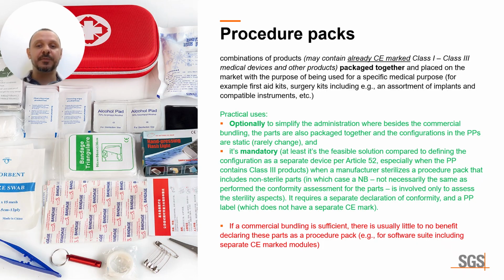The definition of procedure pack may also be mandatory, at least it's the feasible solution compared to defining the configuration as a separate device per Article 52, especially when the procedure pack contains Class 3 products. When a manufacturer sterilizes a procedure pack that includes non-sterile parts, the notified body, which may be a different one that performed the conformity assessment for the parts, is involved only to assess the sterility aspects.